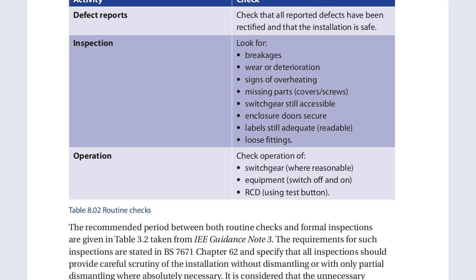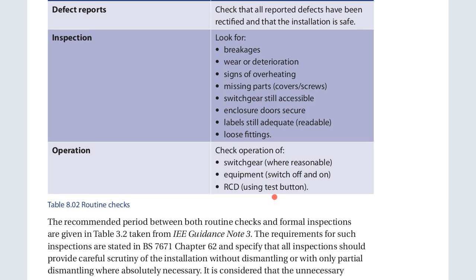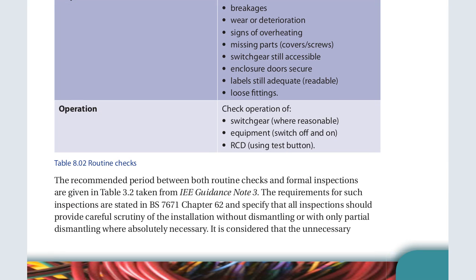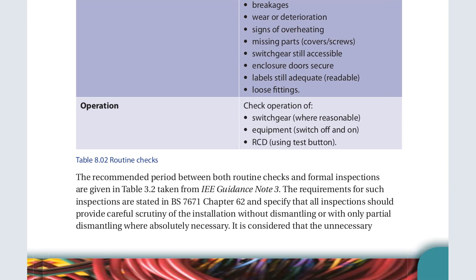We check for enclosures, like the doors, and that the doors are secure. We check for labels that are still adequate and readable, and for loose fittings. We also check operation. What do we check in operation? We check if the switchgear is operating reasonably. We check for equipment that is switching off and on. There are the RCDs, which we check using the test button.